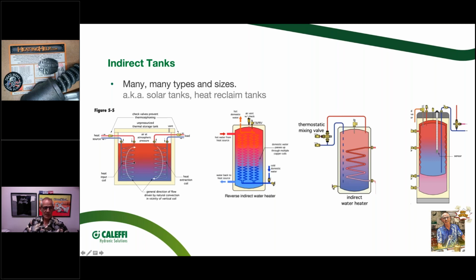There are some formulas out there for the heat exchange here. It gets a little tricky figuring out a heat exchange rate when you have a tank of still water, and not only still water, but a stratified tank. As the coil sees the cold temperature down here, the heat exchange is going to be different than at the top of the tank where it's warm.